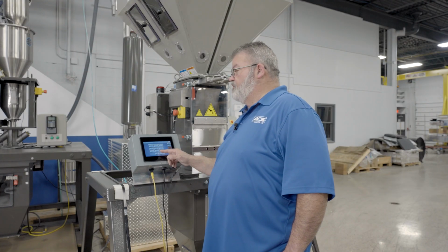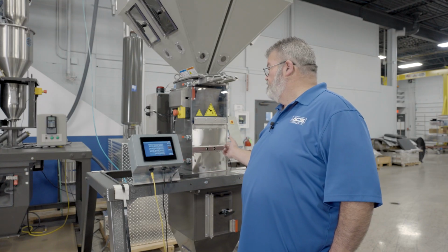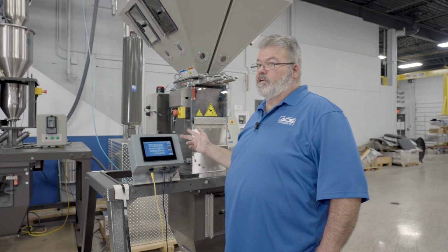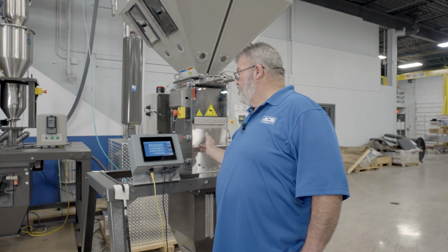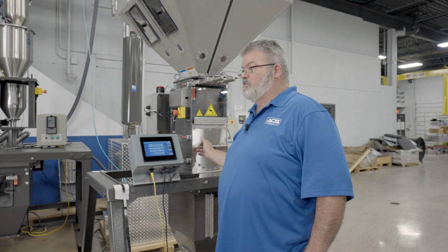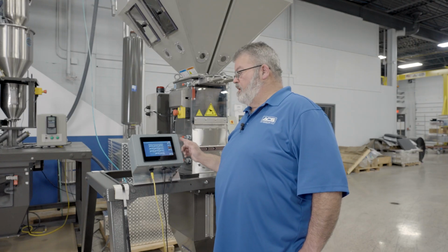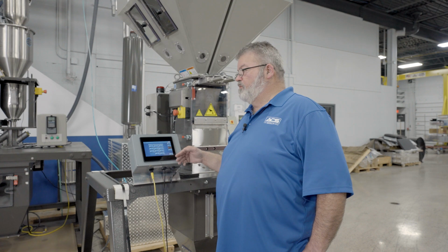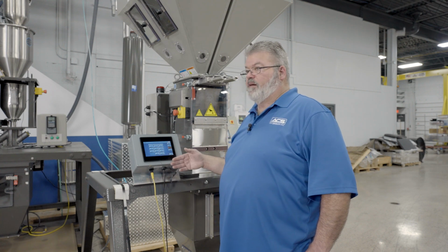We have a feature, if you want, you can have a mixer failure alarm. There's 2 ways we do it, a dry contact on the motor control protector, or you can add an inductive proximity sensor to the mix chamber to sense the mixer turning. Either way, if you enable that alarm and it fails, you can have it either stop or just alarm.